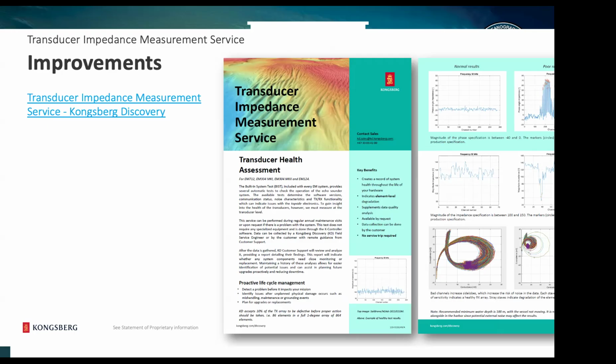What this does is measure things that the BIST doesn't measure. Your BIST test really looks at the connectivity of all the components of the system, making sure everything is registering correctly, checks out all your versions, your TX channels, makes sure the boards are sound, measures your noise levels from your RX array, things of that nature.